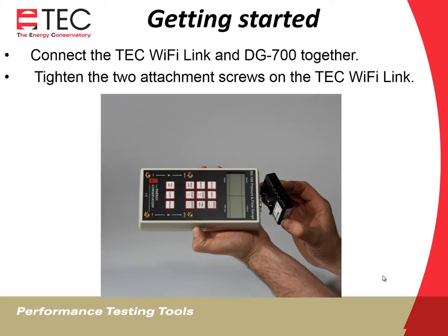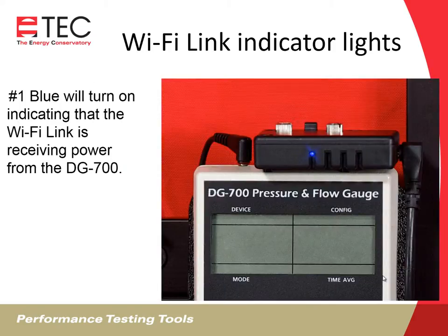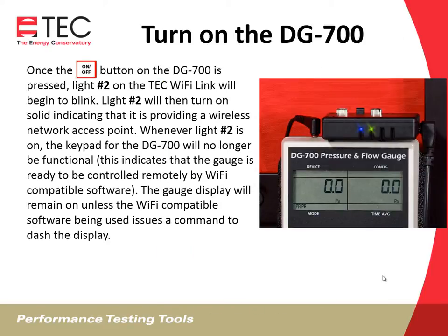Getting started: connect the TEC Wi-Fi Link and the DG700 together and tighten the two attachment screws. Attach the power jumper cable between the Wi-Fi Link and the DG700. The number one blue light will turn on, indicating that the Wi-Fi Link is receiving power. Once the on-off button on the DG700 is pressed, light number two will begin to blink, then turn solid, indicating it's providing a wireless network access point. Whenever light two is on, the DG700 keypad will no longer be functional — the gauge is ready to be controlled remotely. The DG700 will beep when connected. The gauge display will remain on unless the Wi-Fi compatible software issues a command to dash the display. If you're using TECTite software, the display will dash. If you're using the Apple software, the display will remain on.